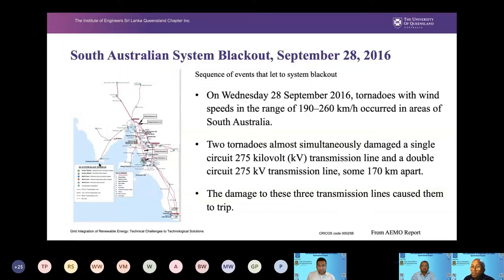So there were tornadoes. This was unusual during that time of the year. Wind speeds ranging from 190 to 260 kilometers per hour occurred, and naturally these are not friendly for the transmission system. These two tornadoes simultaneously damaged a single circuit and also a double circuit transmission line, creating a lot of faults in the system.